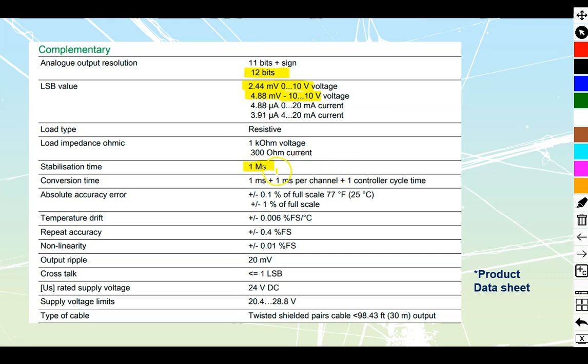Stabilization time is going to take us a millisecond to reach values. Conversion time is how long it's going to take us to make the stabilization plus add in the number of channels. So if we've got two inputs, it's going to be two channels plus the controller cycle time.